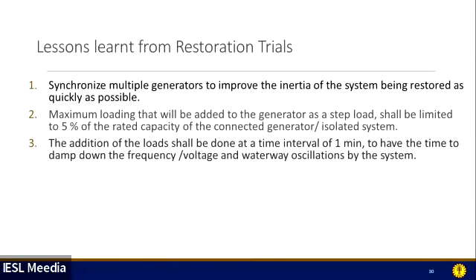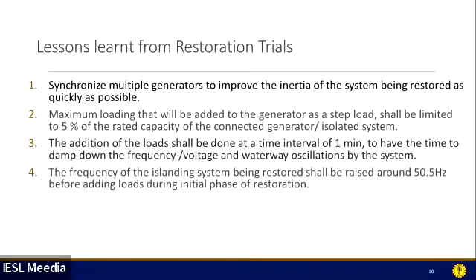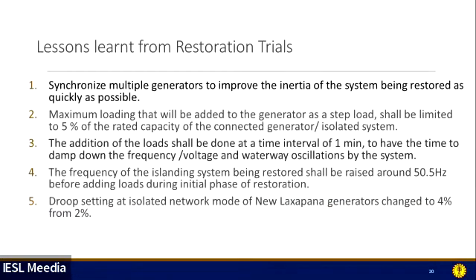Then the addition of loads shall be done at a minimum interval of 1 minute, allowing some time for the frequency to stabilize. Before adding any load, since the frequency goes down during load addition, generally we raise the frequency a little bit high. Then some generator technical characteristic changes were identified during the restoration process. Accordingly, the governor setting of New Laxapana at the isolated network port has been changed to 4%. So those are the findings.